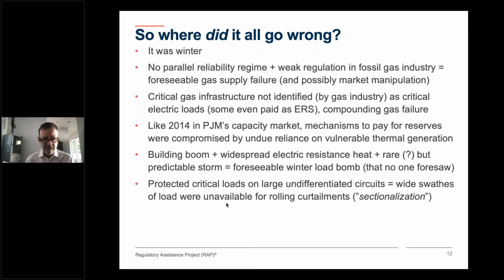There's been discussion in forums at FERC and elsewhere about the fact that Texas has very large undifferentiated distribution circuits. Circuits with protected loads, hospitals, fire stations, and so on, also had a lot of other load that could and should have been included in rolling curtailments, but wasn't available because it was on these large undifferentiated circuits. So what could have been a less severe event with rolling curtailments of smaller amounts of load turned into a sustained 70-hour curtailment instead.